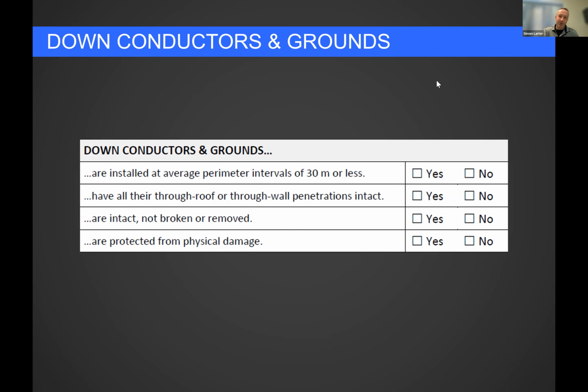But again, we've got that wiggle room with 'where practicable.' Even on the outside of a building, 300 millimeters away on the inside past the curtain wall there could be electrical wires. There's no real enforceable way to always keep a lightning down conductor 2 meters from every other electrical wire. That phrase gives everybody peace of mind because you can't enforce it. You just do your best and don't deliberately route conductors right next to others.